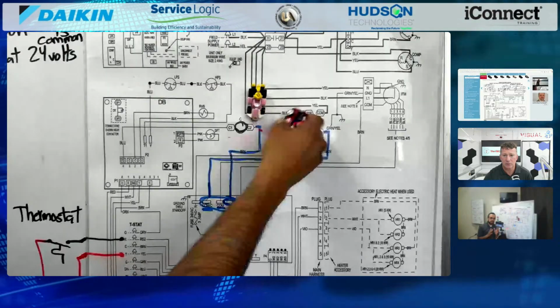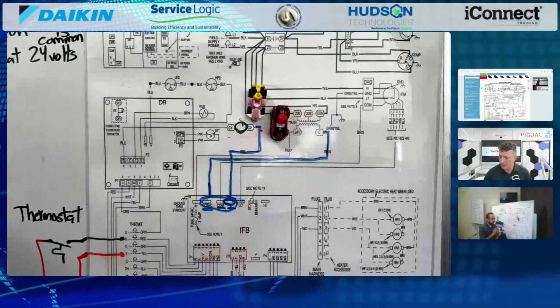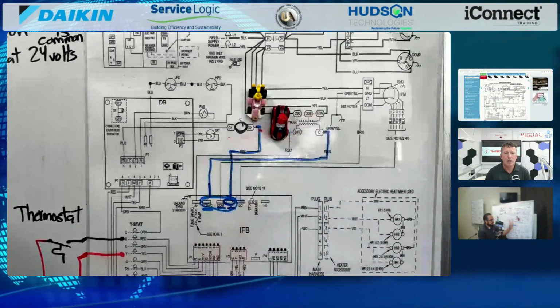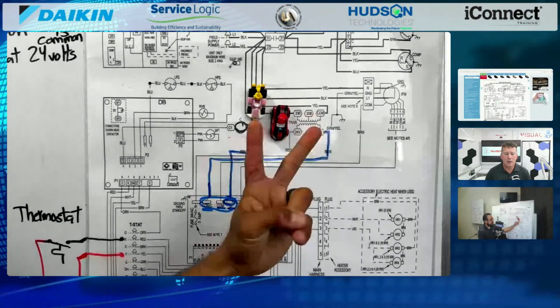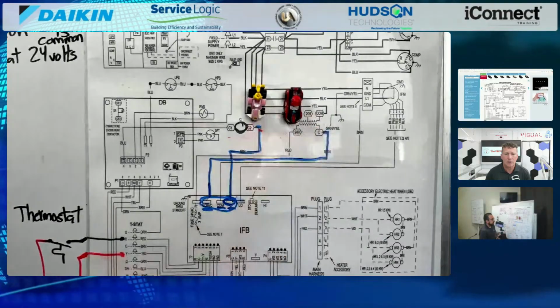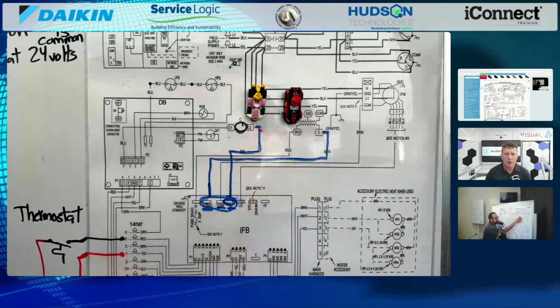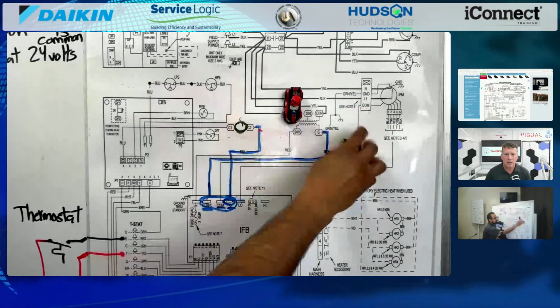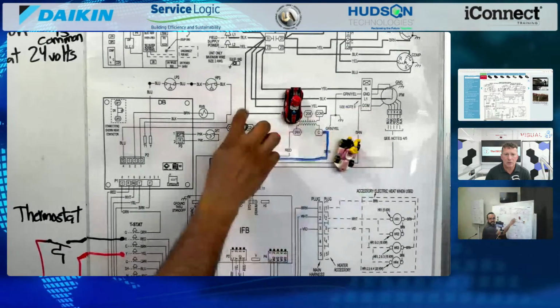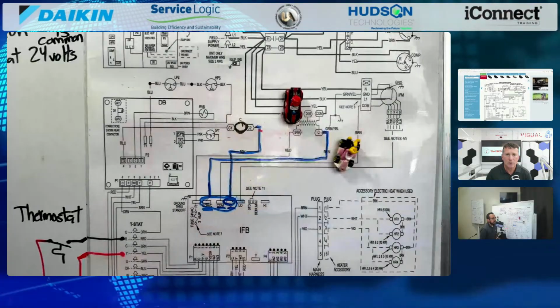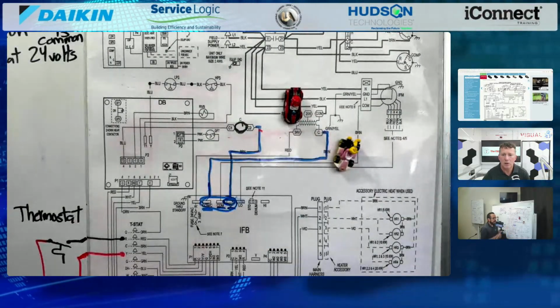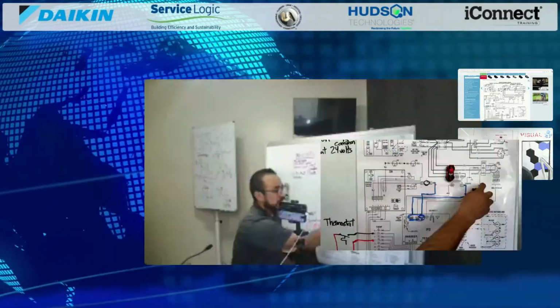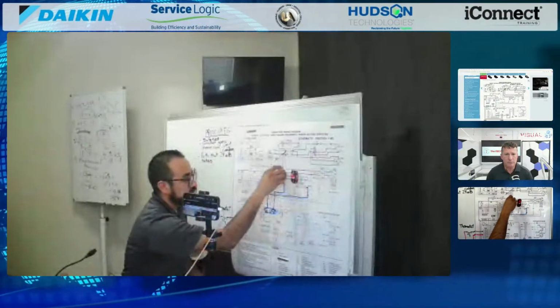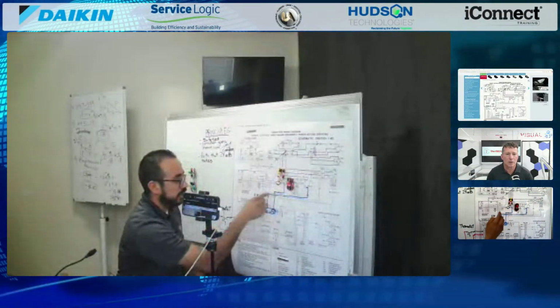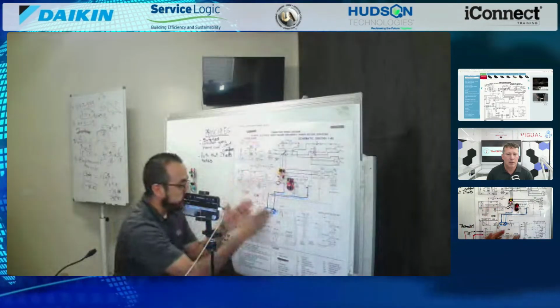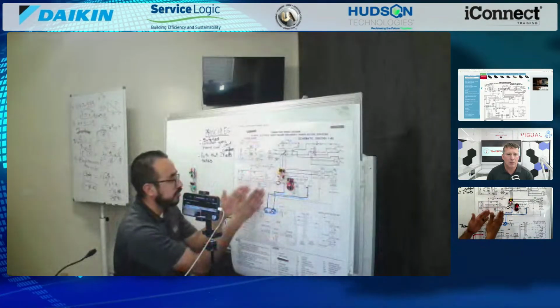At least focusing on just the low voltage, not high voltage - we just have two wires, common and 24 volts. I always use Mario for 24 volts, and I'll use Peach as common, because Mario has to work hard to make it to the contactor coil, to make it to the load. So Mario needs to take a path, and Peach, I'll use as common - she's already here. Mario is the one that needs to travel through the board, through the safeties, through the thermostat to make it to the contactor coil.